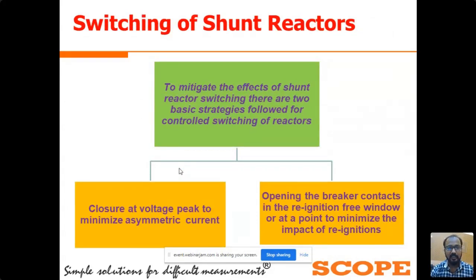For the switching of shunt reactors, we basically use two strategies. For closing, as we know, a shunt reactor is an inductive load, and inductive loads have the property that they oppose sudden changes in current. So if we switch inductive loads near the current peak, they produce high transients in the system. So we try to open or close the shunt reactor near current zero. At the time of closing, the CB is in open condition, so there is no current flowing through the system. We don't have the reference from the CTs, but we have the reference from the PTs.